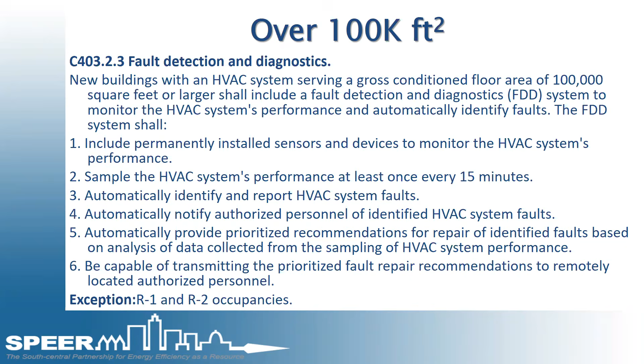More and more controls, more and more smart buildings. As technology gets easier and better and cheaper, it makes sense, because you can save a whole lot of energy just by making sure that your economizer is not stuck wide open in August, getting those fault detections, sampling that HVAC system performance every 15 minutes and sending a report. Over 100,000 square feet, that's what they're going to have.